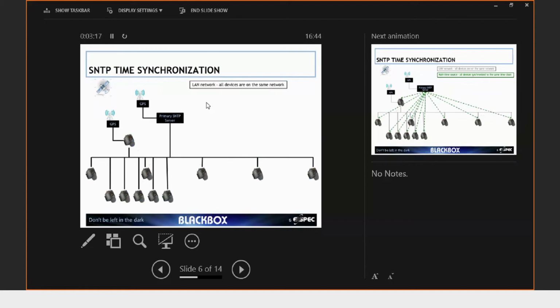So you connect one unit, and this unit can also be used as the SNTP time source for the other units. However, the instrument is designed to be a power quality analyzer and recorder, not an SNTP server. So we do not want it to influence the performance of the instrument, so it is limited to providing a time source for not more than 5 units.